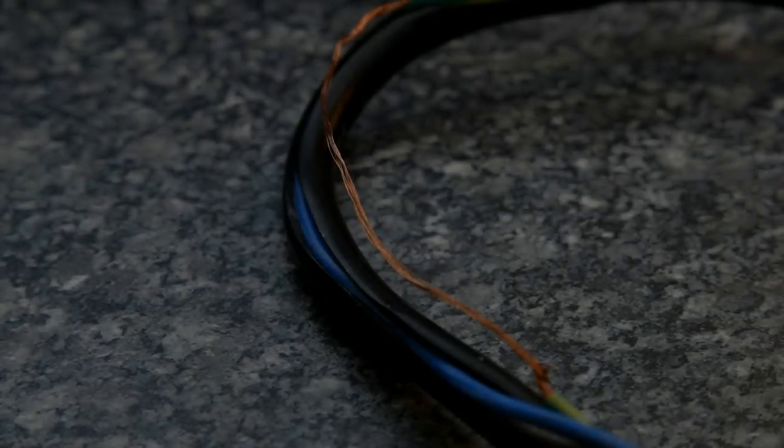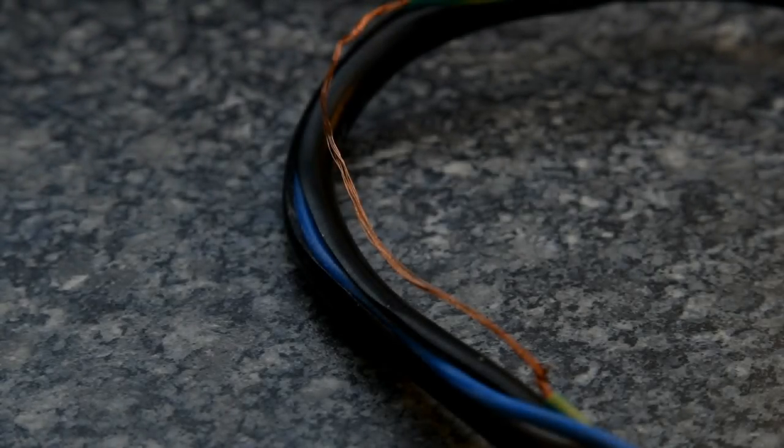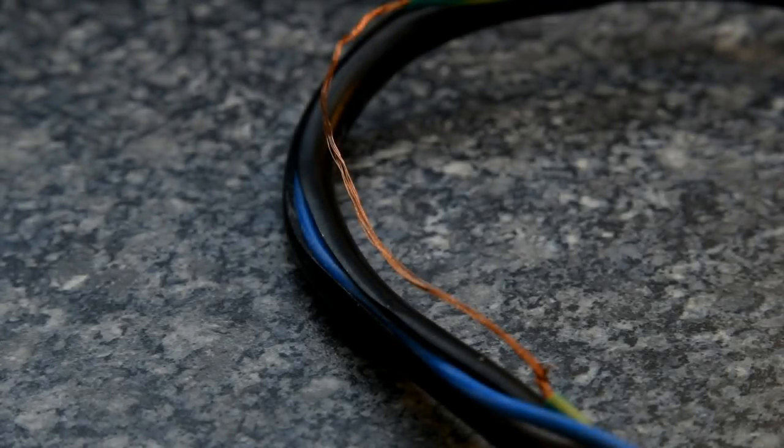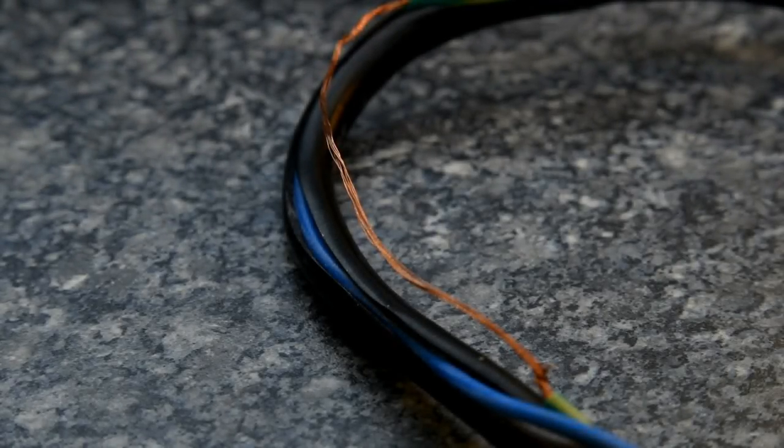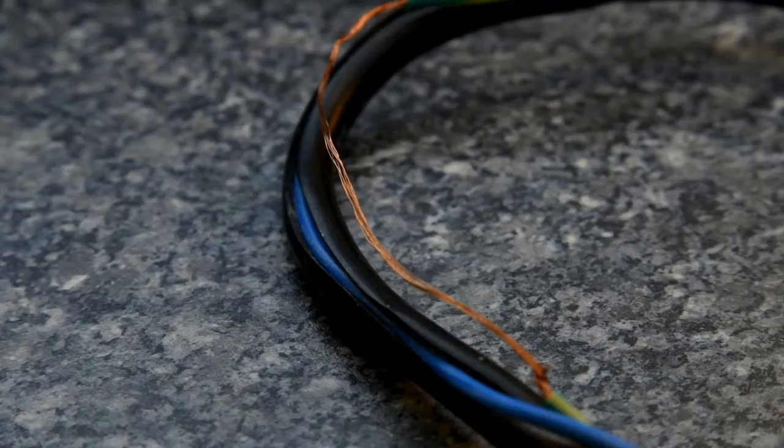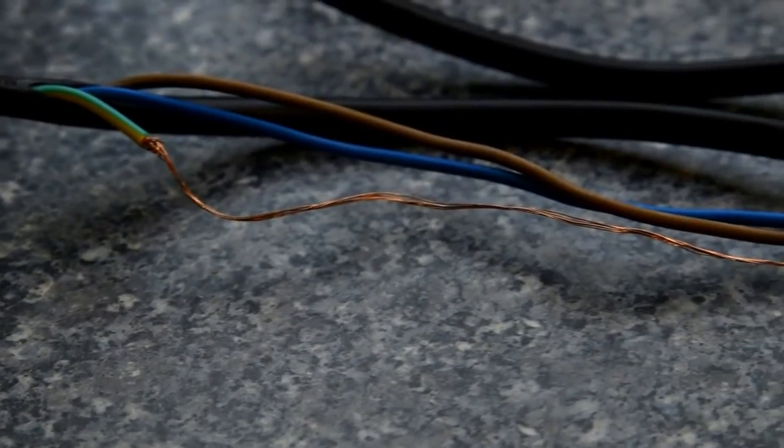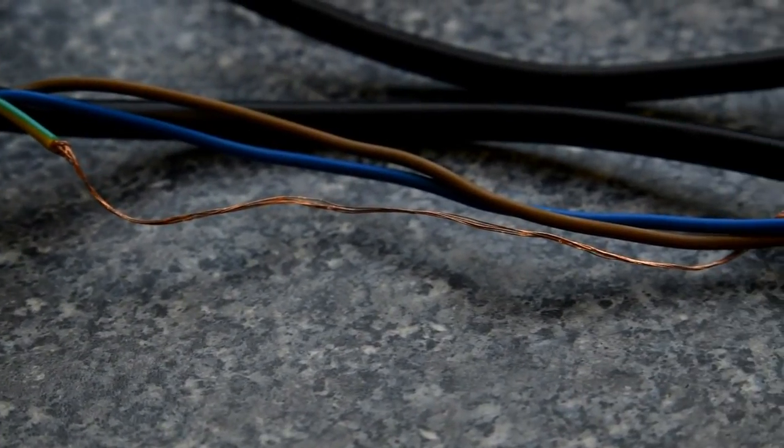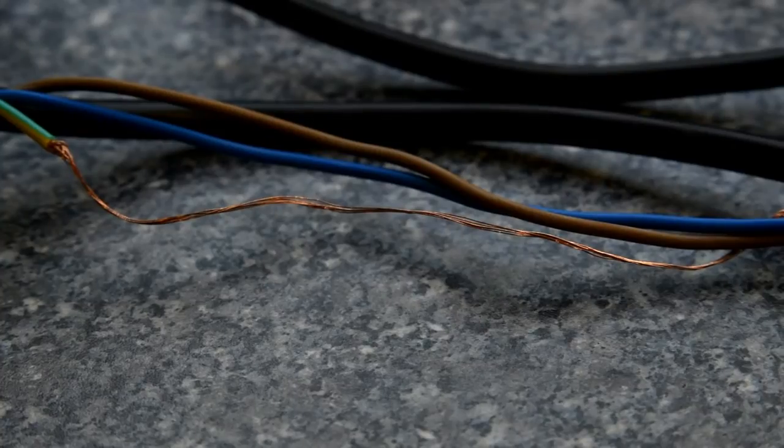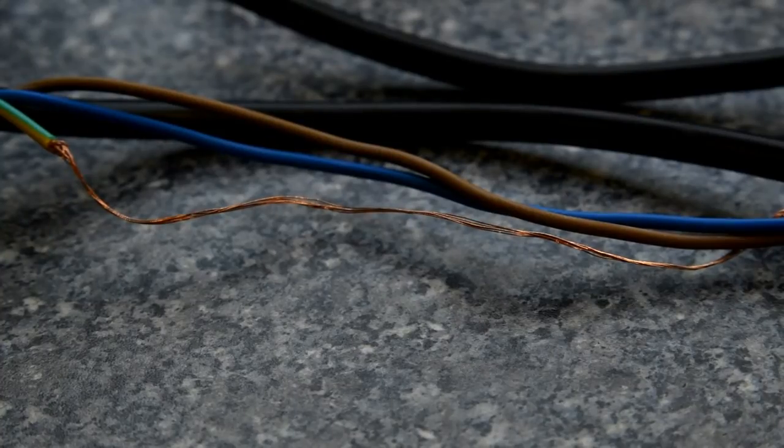Here's our soft test. Passes just fine. No sweat. Despite the extensive damage, the test passed it because it isn't really testing the strength and integrity of the earth wire.